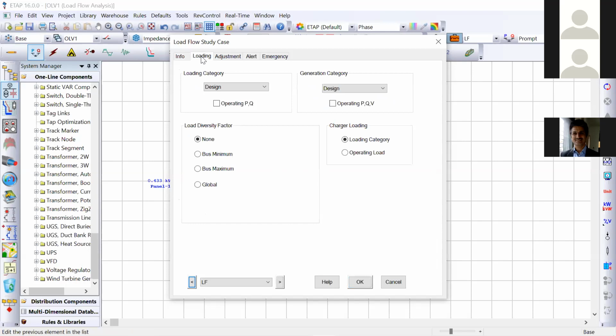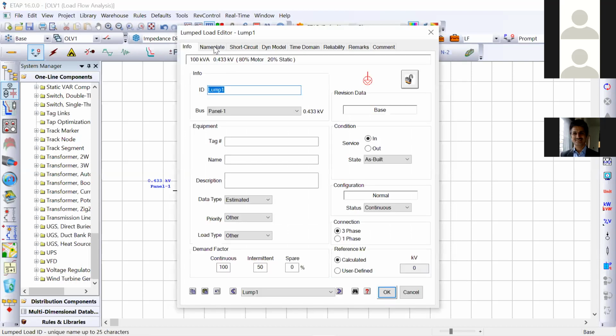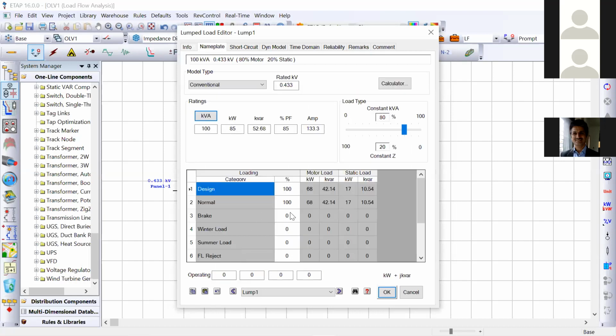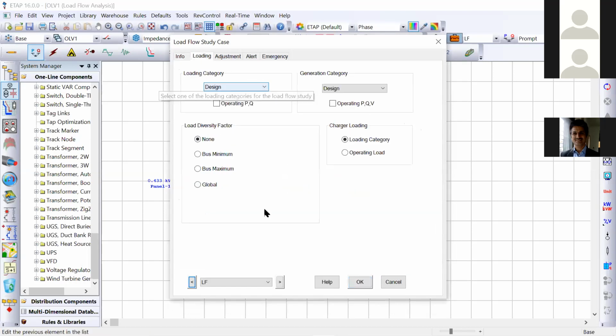This is called a loading category menu for the load flow study case. Here you choose whether you want to perform the calculation on a loading category of the load, maybe a normal load, a winter load, or a summer load. So different loading categories are given. If you check this lump load, on the nameplate you are getting these many categories. You can define design category as 100%, normal category as 100%, brake category as say 200%, winter loading category as say 50%. You can perform load flow corresponding to that particular category. Presently we are going with the design category.